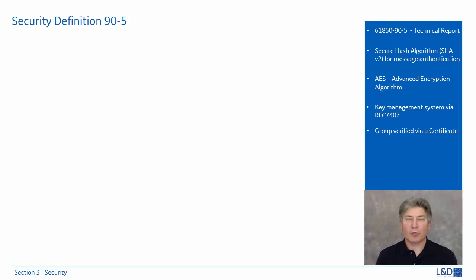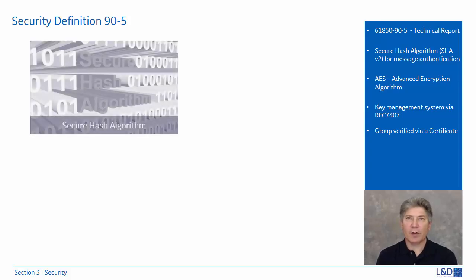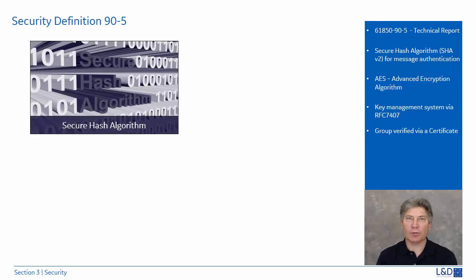The technical report 61850-90-5 defines how the routable GOOSE must be secured over a wide area network. First, it defines a secure hash algorithm. It uses SHA-2, known as Secure Hash Algorithm version 2, which is used for message authentication and integrity — similar to a CRC that places tamper detection on the message.